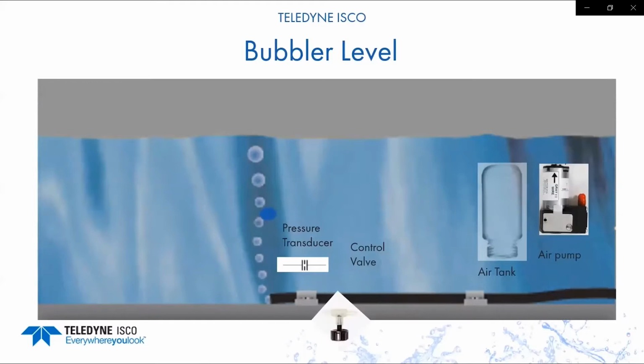And then with the ISCO bubbler system, if the bubble line starts to get clogged due to sediment and stuff, they have an automatic purge system that will then send a large burst of air out to automatically clean this. If your bubbler flow meter does not have this feature, for regular maintenance you'd have to go out there with an air tank, remove the air line, and then blow some air through there to try to clear out any debris that could be plugging that. And what you'll find is that if you have debris covering the end of that bubble line, you're going to see that your level readings are going to start to go higher than the actual water depth, and your flow rate will then also go higher.